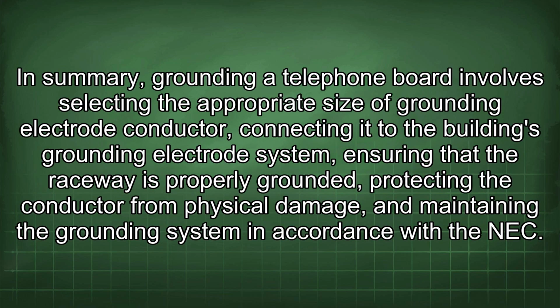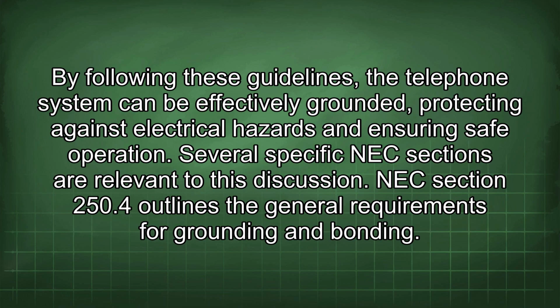In summary, grounding a telephone board involves selecting the appropriate size of grounding electrode conductor, connecting it to the building's grounding electrode system, ensuring that the raceway is properly grounded, protecting the conductor from physical damage, and maintaining the grounding system in accordance with the NEC. By following these guidelines, the telephone system can be effectively grounded, protecting against electrical hazards and ensuring safe operation.